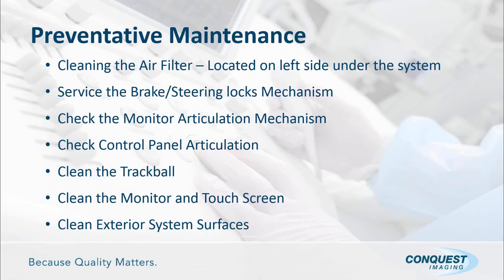Check the monitor articulation mechanism. In just a couple minutes, I have some slides that will show you exactly how to perform this if it's not right. In a PM, you're checking it. If it's not adjusted correctly, we will show you a service adjustment on how to do that. Same thing with the control panel articulation. You need to clean the trackball. The trackball is very easy to clean on this. It has a ring that you rotate a quarter of a turn and pop off the ring and get the trackball out. There's no need to remove the control panel or anything else, as in several other systems.